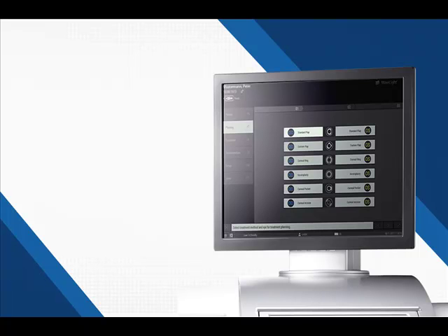It will not activate the software. And if you use a white one for LASIK, you've wasted a patient interface. It will not activate the software, and it cannot be reused either. So it's lost, if a mistake is made that way. It's locked. It's a one-way street. It will not allow it.